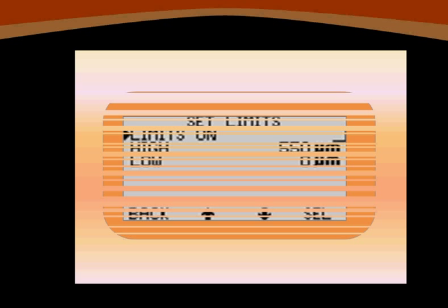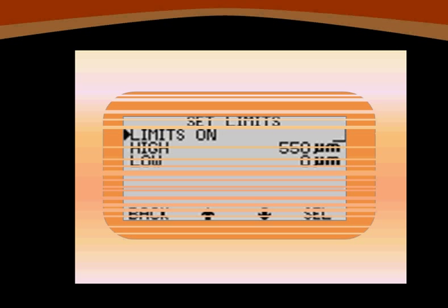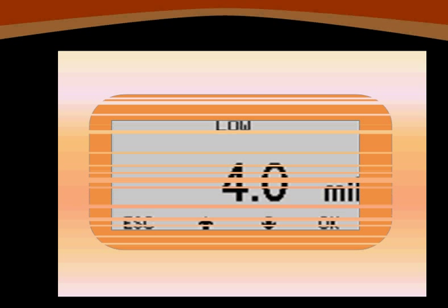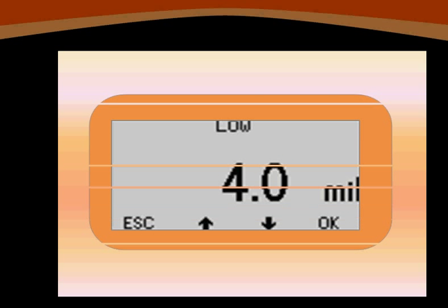Let's start with the lower reading boundary first. Arrow down to low and press the select key. Use the up or down arrows to reach the value you need and press OK. Repeat the process to set your high limit.